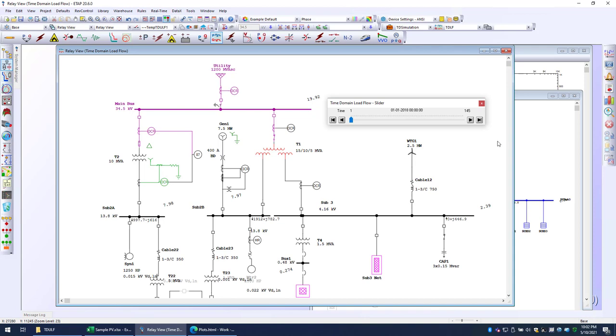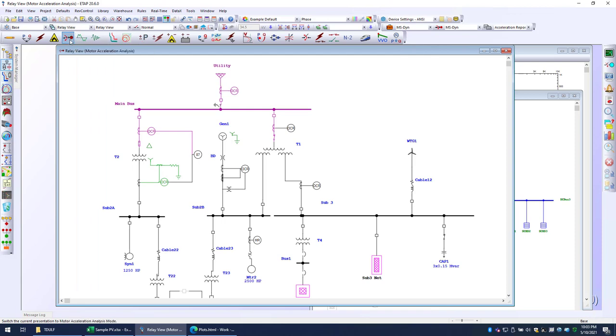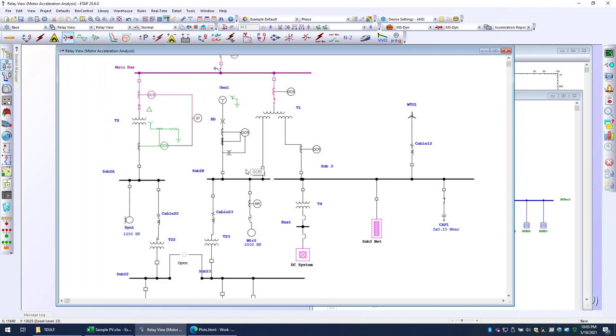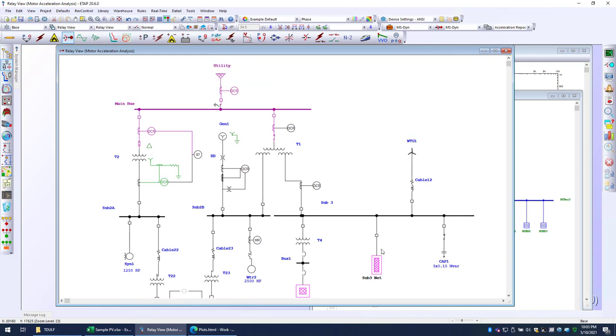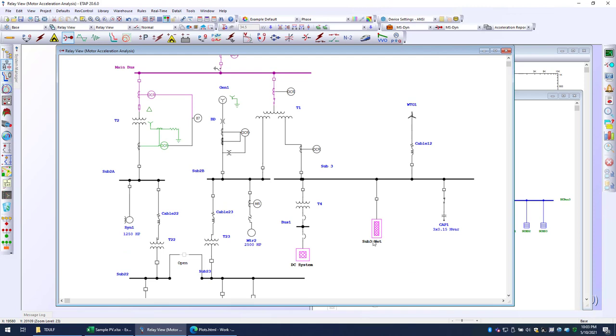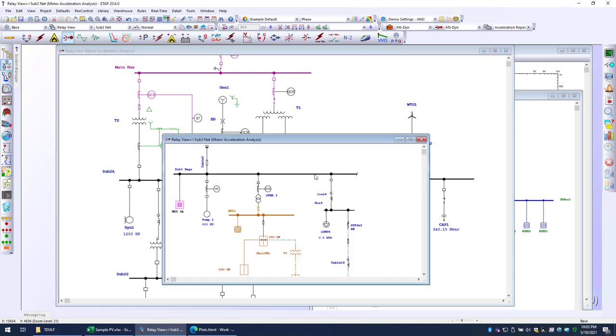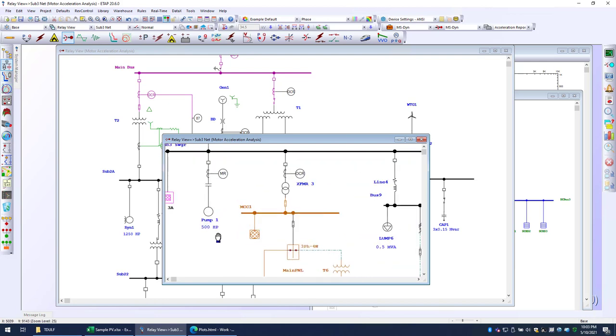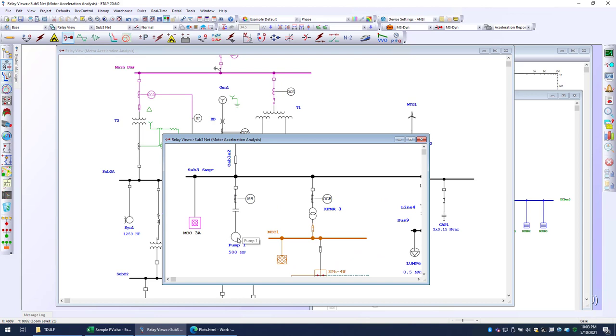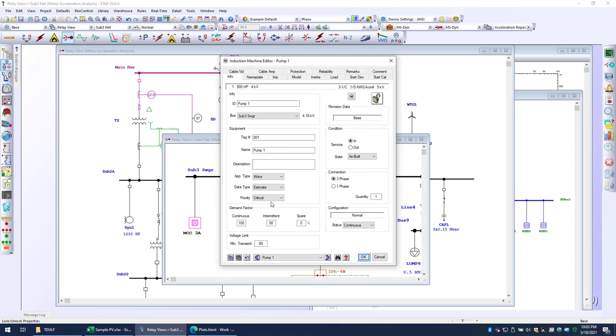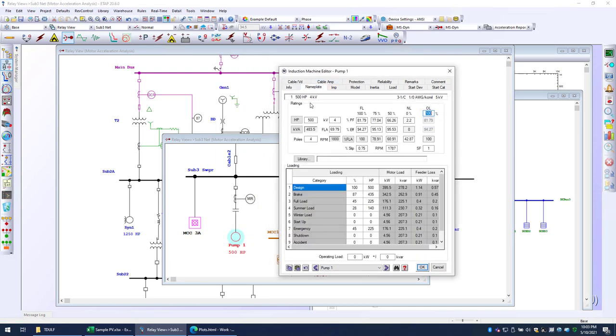Now, let's take a look at motor starting analysis. In the same way that we went over to the time domain load flow, let's go back to the motor acceleration. This is a transient; we're going to perform a transient motor starting. The first thing I'd like to do is show you how we enter some of this information. The single line diagram is organized in composite networks into the main. This is the main power distribution of the system. I'm going to click on this composite network to show you a little more detail for this particular substation location. Let's take a look at this particular 500 horsepower medium voltage, 5 kV rated pump, and double click on it to show you the pretty standard nameplate.